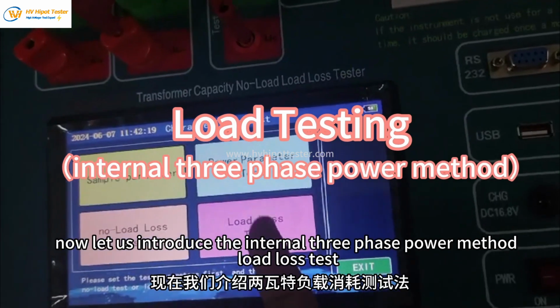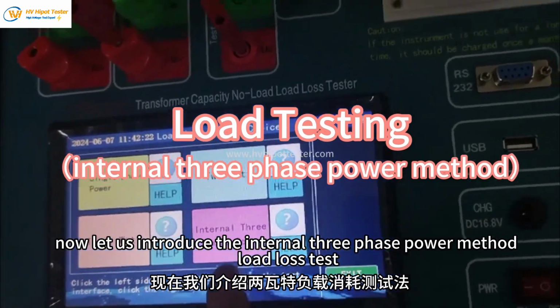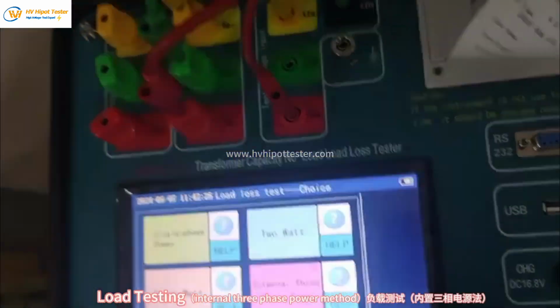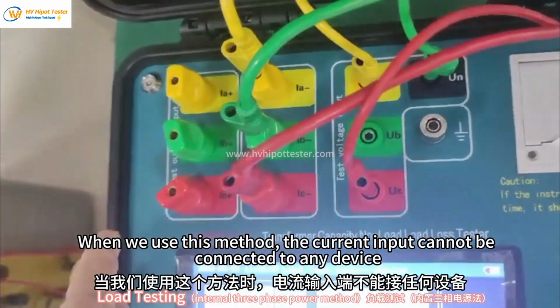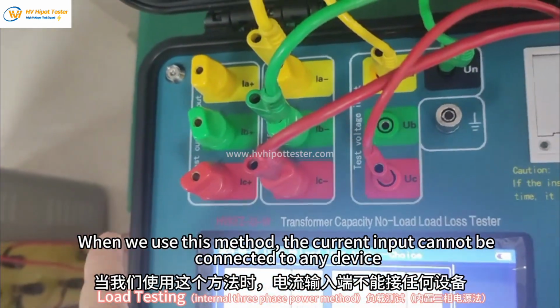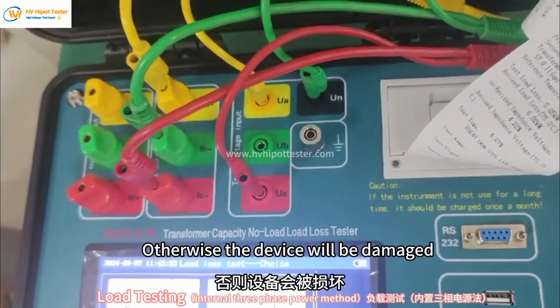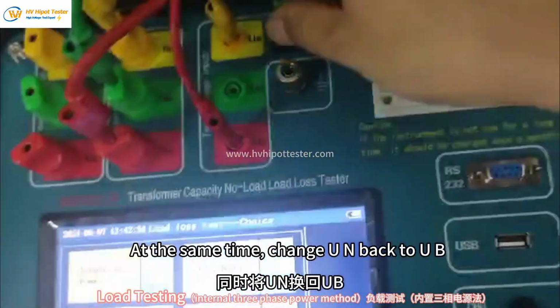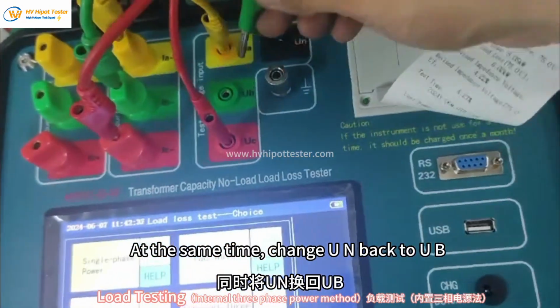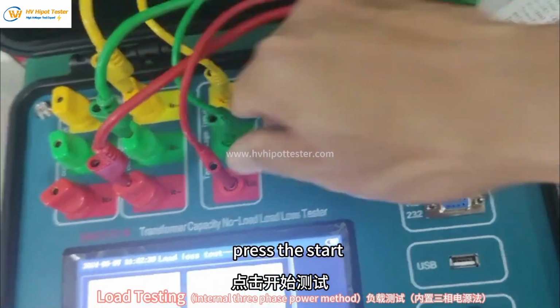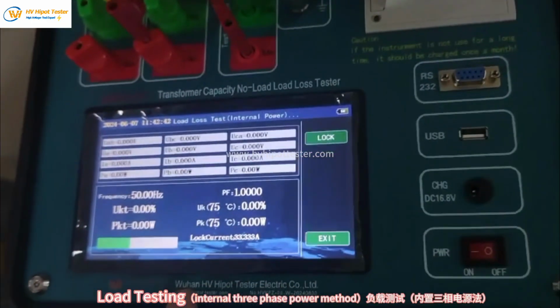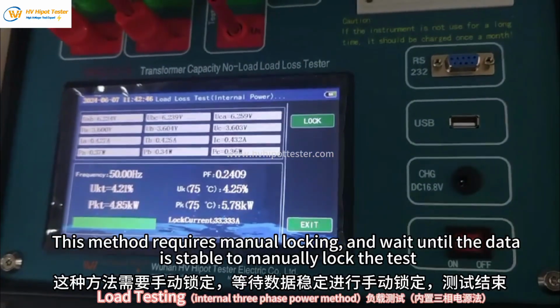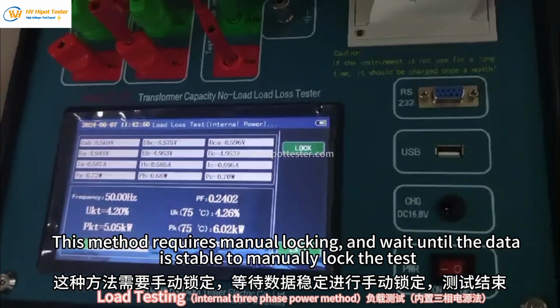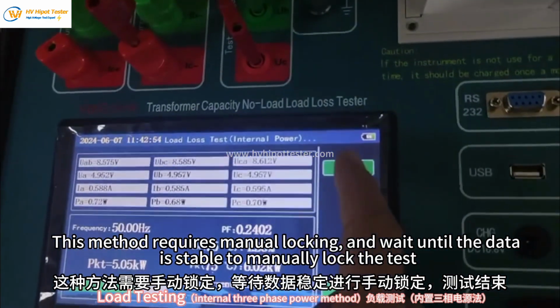Now let us introduce the internal three-phase power method load loss test. When we use this method, the current input cannot be connected to any device, otherwise the device will be damaged. At the same time, change UN back to UB. Press start. This method requires manual locking: wait until the data is stable, then manually lock the test.